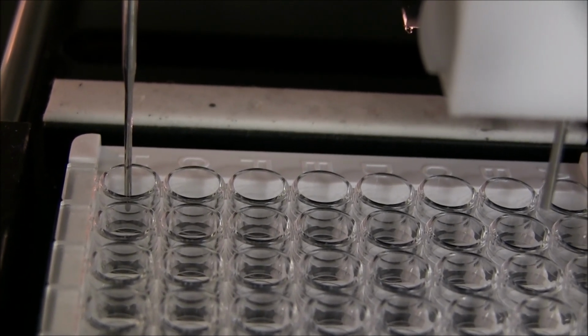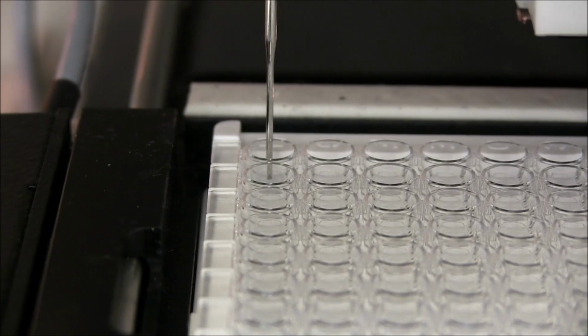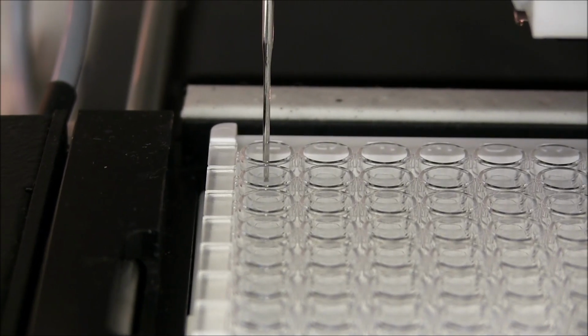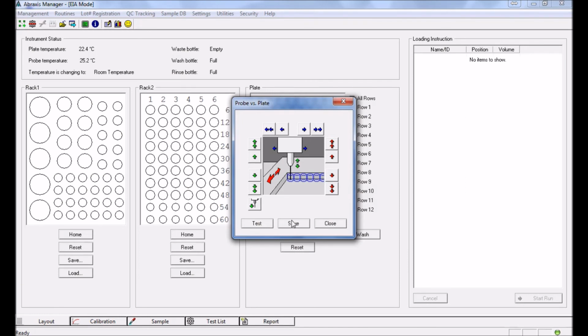When aligning the probe along the z-axis by way of the green arrows, be sure the probe is not touching the bottom of the well. Ideally, the tip of the probe should be no deeper than halfway into the depth of the well. When satisfied, click Save, then Close.